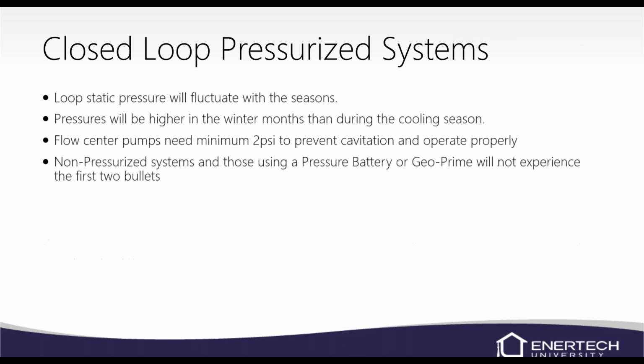On a closed loop pressurized system, the loop static pressure will fluctuate with the seasons. So the pressure is going to be higher in the winter months than during the cooling season. Basically, why that is, in the winter when the water is cold, 30, 40 degrees, it's going to cause that pipe to shrink. It constricts when it's cold. So as it constricts, it pushes on that water and creates higher pressure. In the summer, when you got water temperatures of 90 degrees, it causes that pipe to relax and expand a little bit, and then you can lose some pressure.